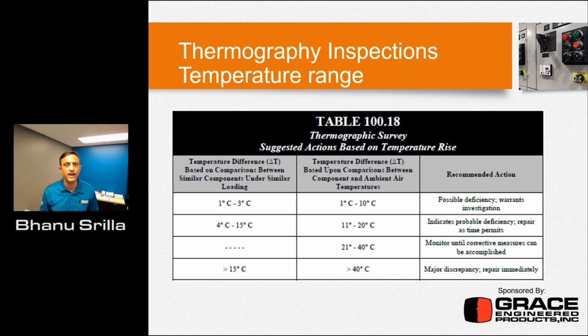If you look at one of the same standards, NFPA 70B refers to insulation degradation over time and how it relates to temperature, right? So a 10 degrees C rise in the operation of the equipment, though it doesn't require an immediate investigation or monitoring, in retrospect is going to affect the overall longevity of the equipment. For example, if the equipment is designed for a 30 year lifetime, and then you run this at 10 degrees C high, that's going to lead you to only 15 years. So your CapEx budget is going to have people rebuy this equipment whenever they need to change it, in 15 years or 30 years, the design operational life, okay?